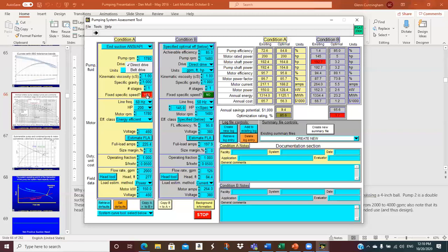For example, a lot of times these vertical turbine pumps are very efficient. But the problem is, if I've got a pump sitting here with a pipe coming in and a pipe going out, I can't replace that with a vertical turbine pump. I'd have to dig a hole in the ground, put in a well, fill it up with water, and stick a vertical turbine pump up there. That's never going to happen. So if you were designing from scratch, you might say, okay, wow, I can get 84.8%. Let me call up my pump supplier and figure out what kind of pump that is, and maybe I'll design my system around it. But if you're working on an existing pump, you can't do that.